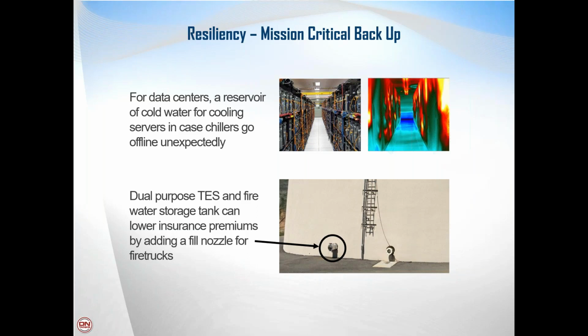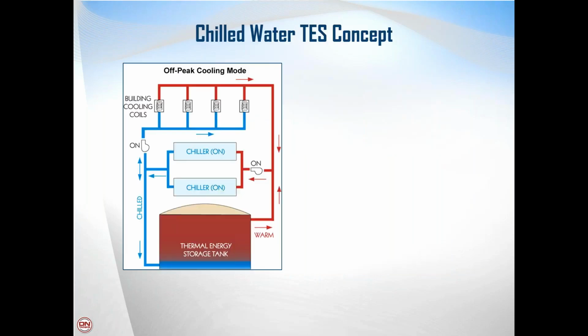And the picture below shows one of our thermal storage tanks with a fire hose nozzle connection on the outside of the tank. And that connection can be used by a fire truck. If there's a situation where there's a fire at a facility or a campus, a fire truck could pull up to this tank, draw water out of the tank, and use it to put out the fire. And many times that is a benefit to the owner, not only to have that reservoir of water available, but it could reduce their insurance premiums just by having that nozzle connected to their tank.